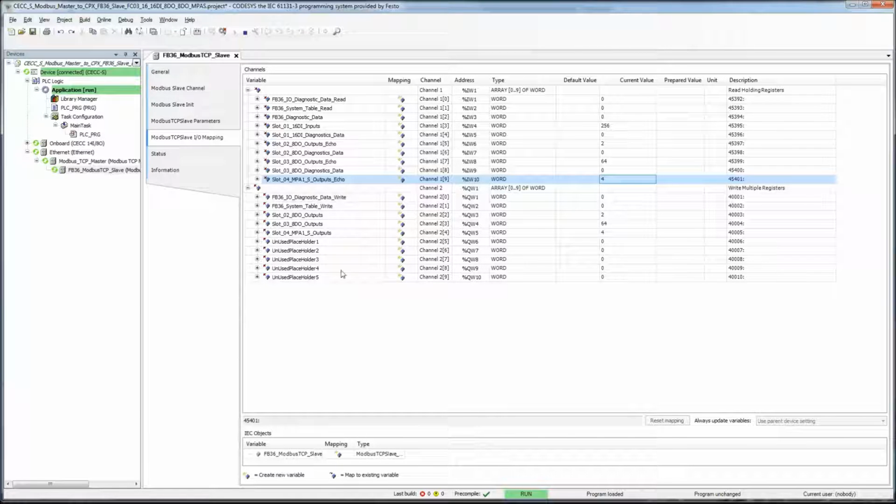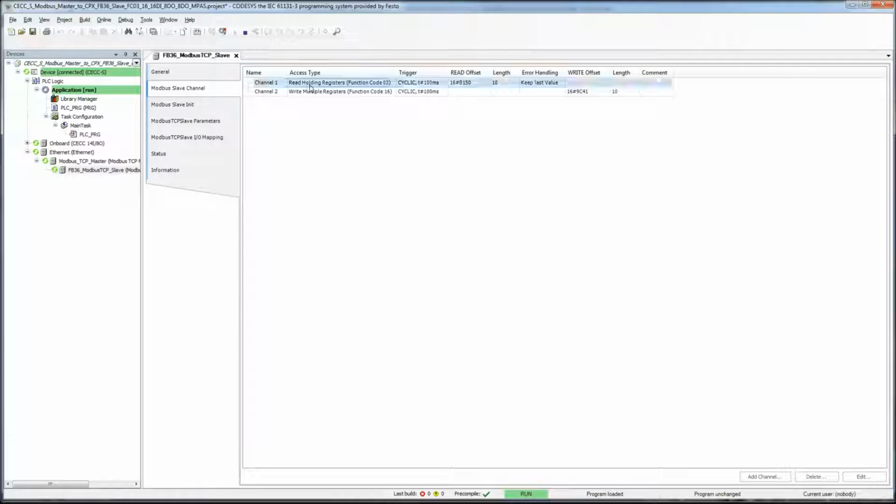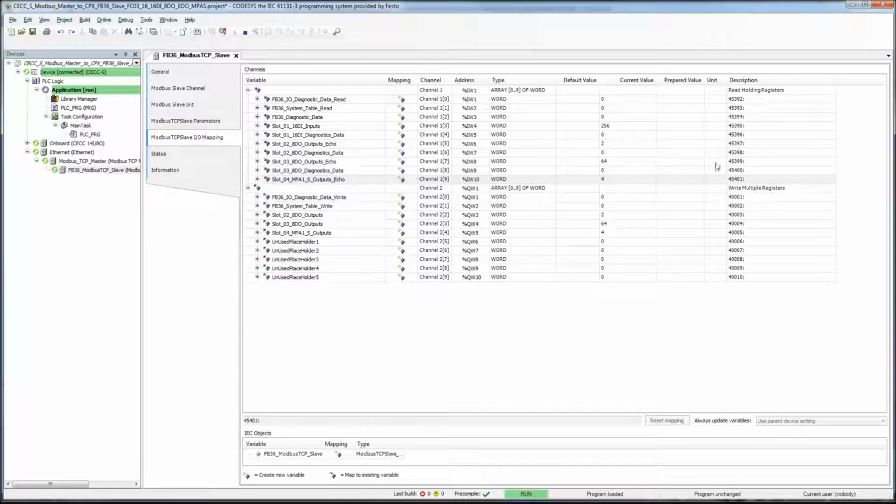Well, I guess one more point worth mentioning is the fact that when you are, in fact, configuring these slaves, if I put in a length of 20, all you're going to do is take up a little more traffic by adding the extra data. It doesn't fault out when there's a data mismatch. So if you have a project where you're constantly changing things and you don't want to have, when you change the length of this offline, sometimes it wants to blow away your descriptions over here or blow this away. It depends on the version of software you have. That's why I just say unused placeholder so that I know that I can modify this project later for whatever I want. And that's it.